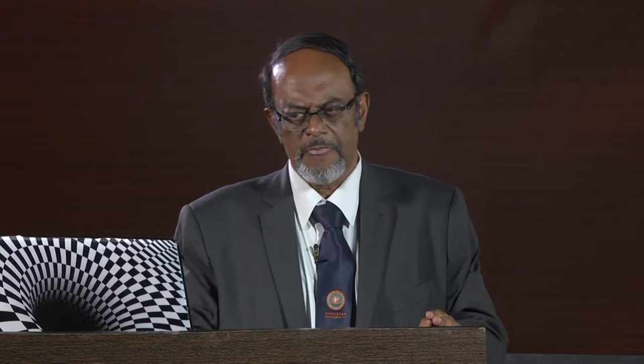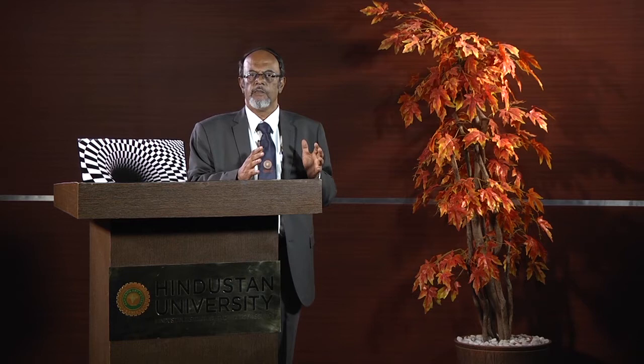In any analog indicating instrument, the effect of the measurement — the quantity that you are going to measure — is converted into a mechanical torque, which is applied onto the pointer and moves it across a calibrated scale. For the total instrument to work, you need various subsystems. The first, obviously, is the deflecting system, which is what creates the pointer movement.